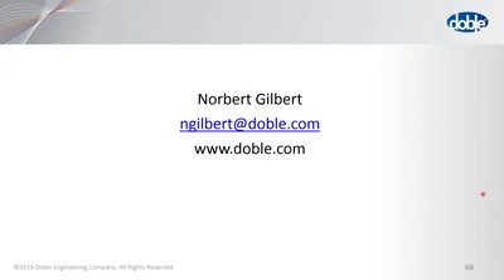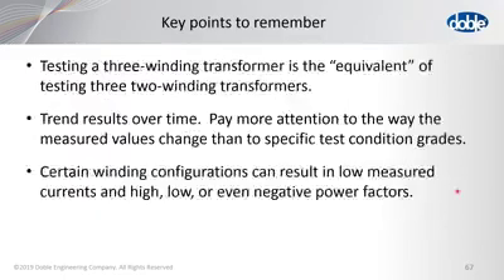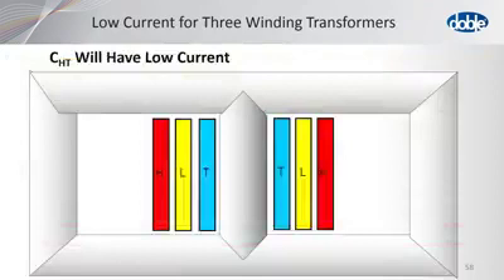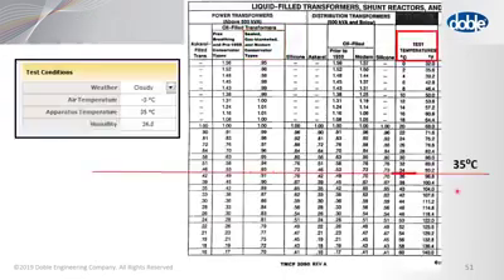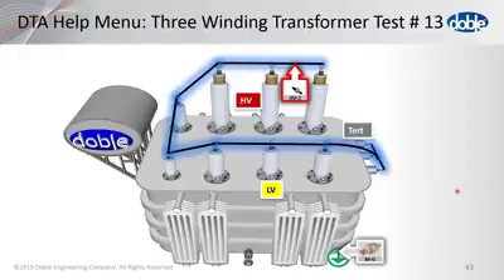So the next one says you have all the capacitors in the measuring circuit on your diagrams. How do you get the capacitor value between the two windings separate from the phase to ground value in the device test? I didn't understand the question, Monty. Could you say it again? It says, in looking at the diagrams, you have all the capacitors showing in the measuring circuit. How do you get the capacitor value between the two windings separate from the phase to ground value in the device test? Yeah, I think I understand.